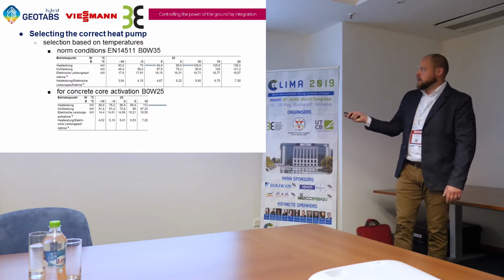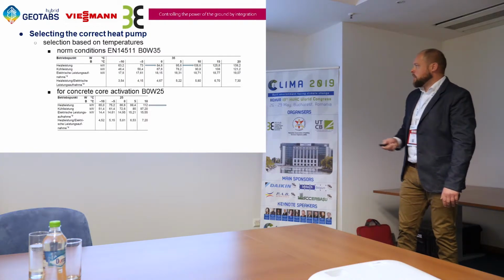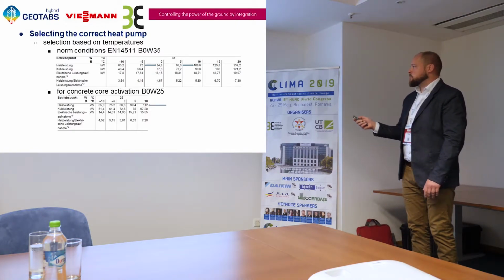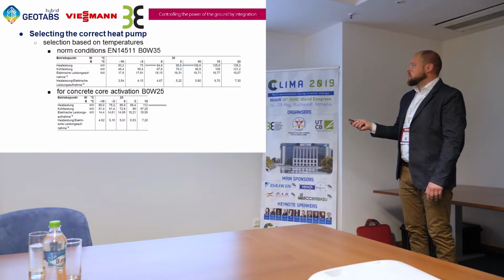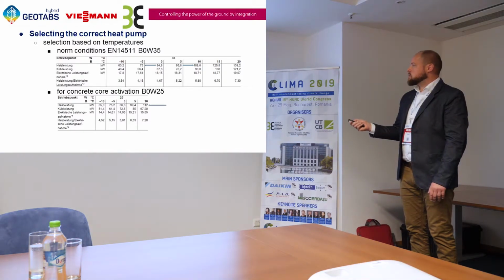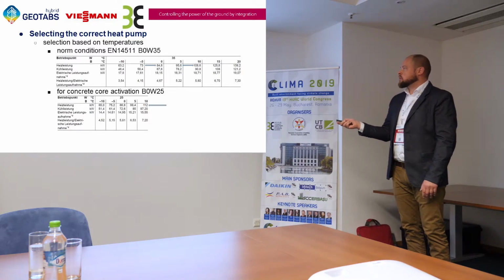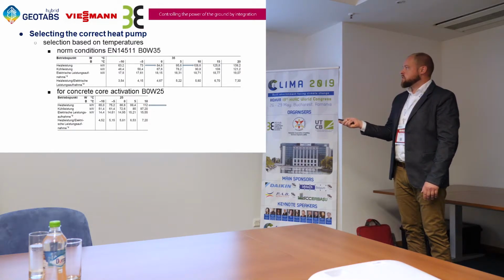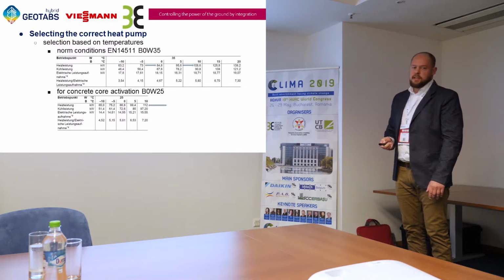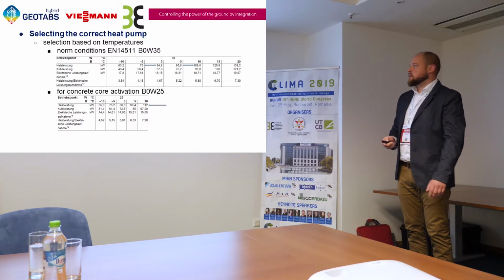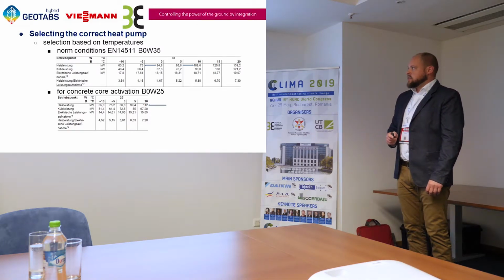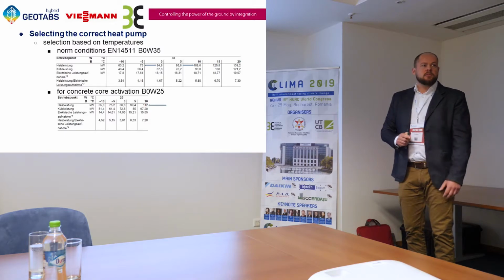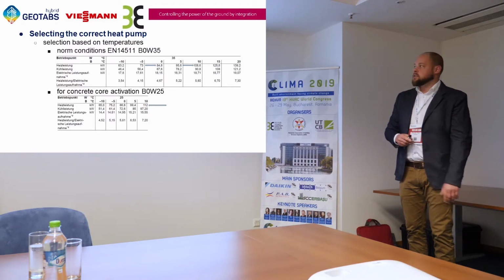If we look at this table, we have a heat pump from Viessmann. The animation is not running. So I wanted to show you the working point, B0W35. We have 84.8 kilowatts of power and the COP of 4.6, 4.7.